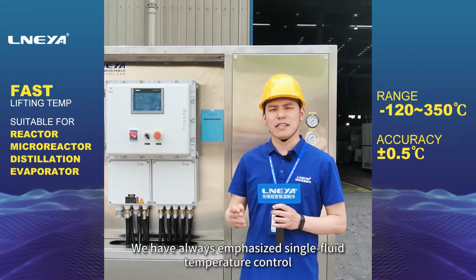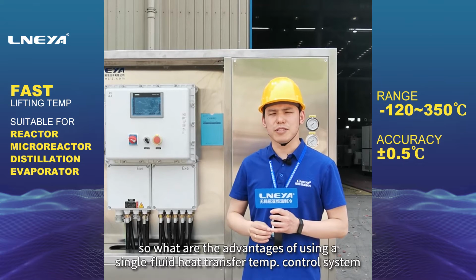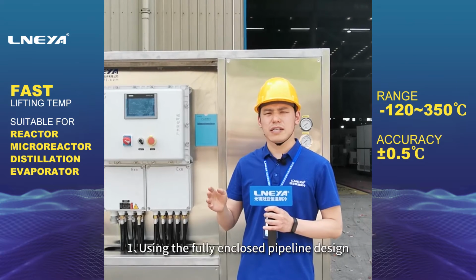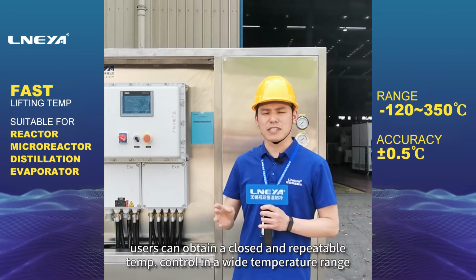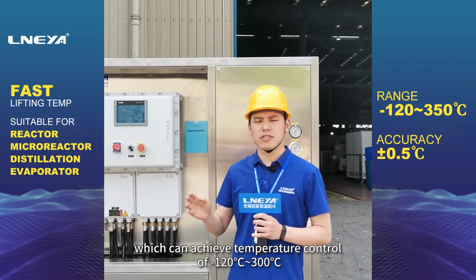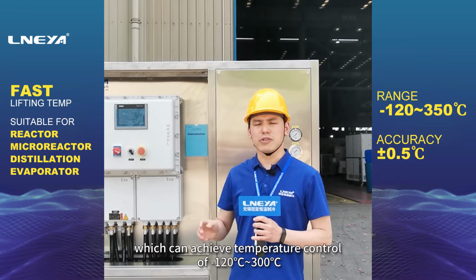We have always emphasized single fluid temperature control, so what are the advantages of using a single fluid heat transfer temperature control system? First, using the fully enclosed pipeline design, users can obtain a closed and repeatable temperature control in a wide temperature range, which can achieve temperature control of -120 degrees Celsius to 300 degrees Celsius.